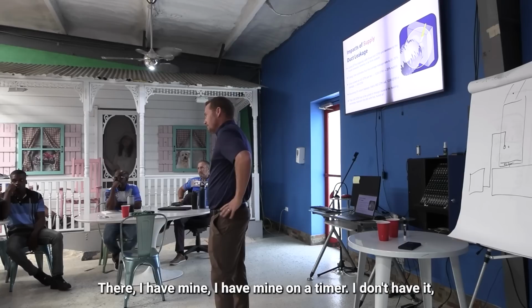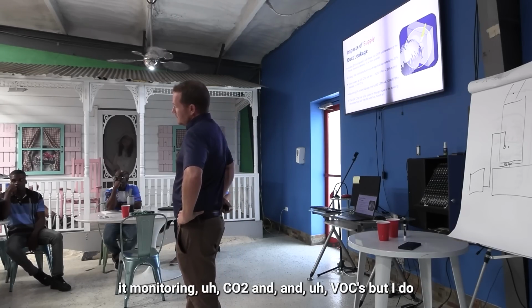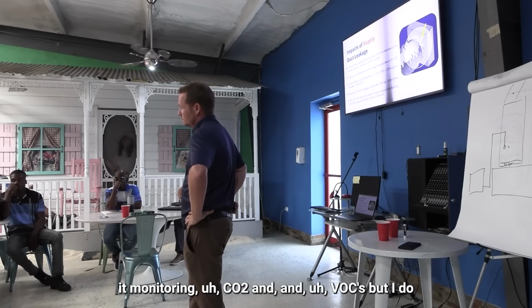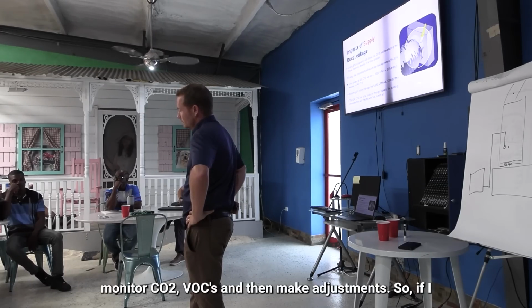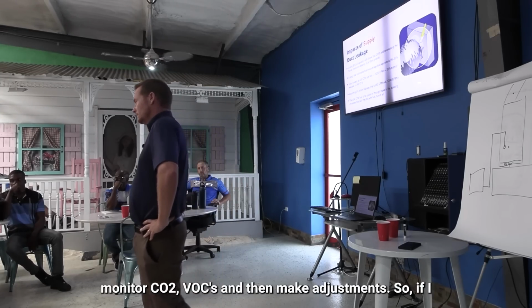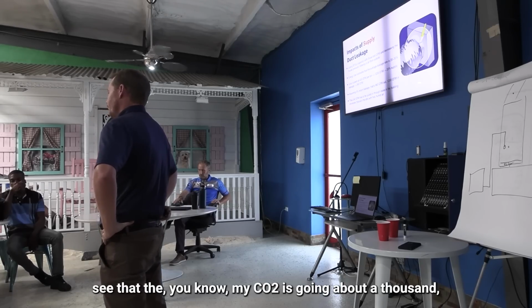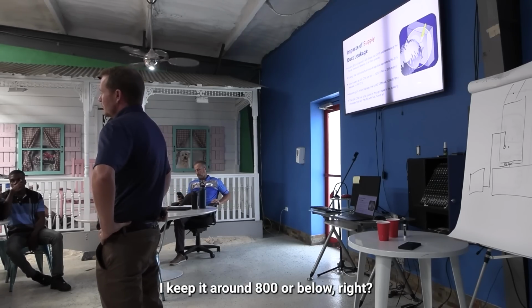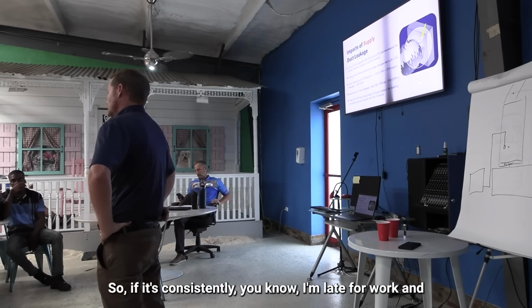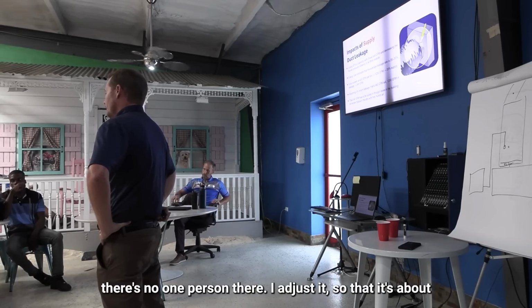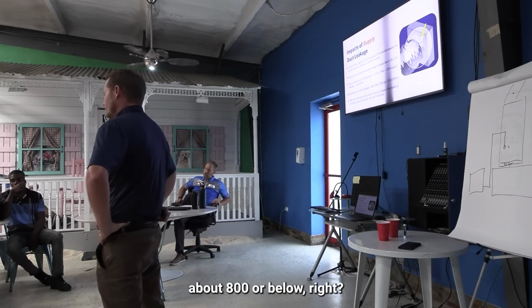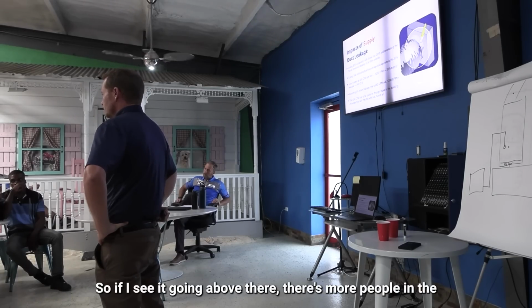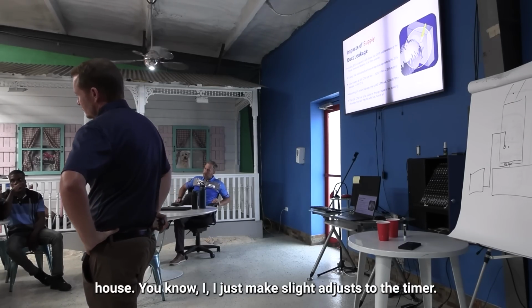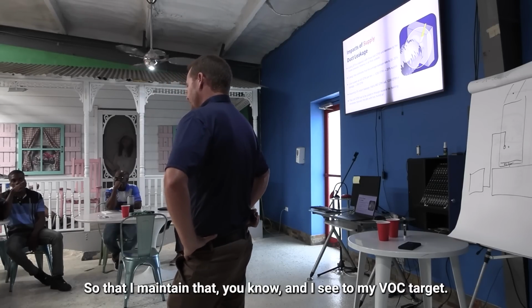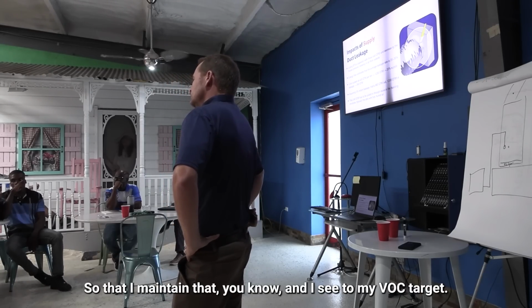Yeah, I have mine on a timer. I don't have something monitoring CO2 and VOCs automatically, but I do monitor CO2 and VOCs and make adjustments. If I see my CO2 going above 1,000, I keep it around 800 or below. If it's consistently low because no one's home, I adjust it so that it stays around 800 or below. If I see it going above that because there's more people in the house, I just make slight adjustments to the timer, so that I'm maintaining a VOC target. And that's the issue with bringing in outdoor air at all.